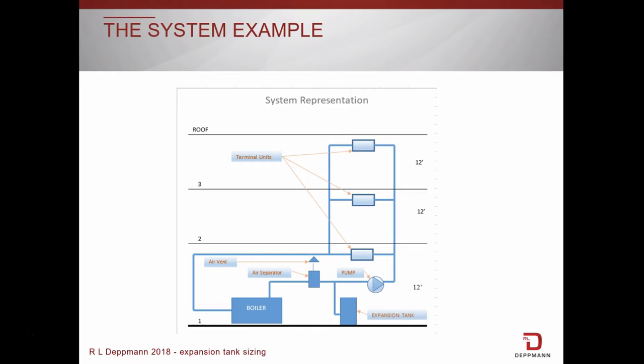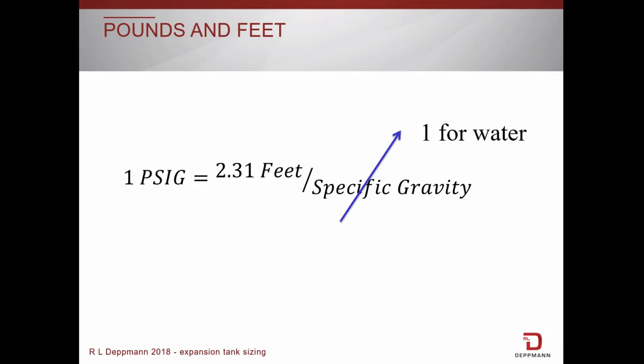The pressure reducing valve, sometimes referred to as a PRV, is used to fill the piping system before the pump is ever started. That fill pressure is called cold fill pressure since we do this before heating the water. So, how do we calculate that pressure?